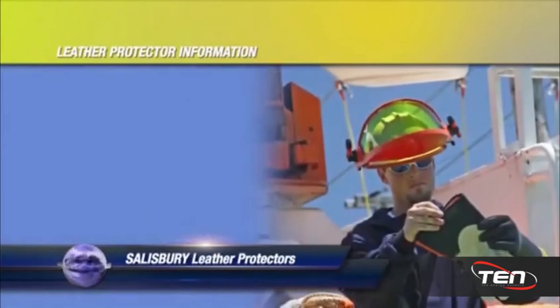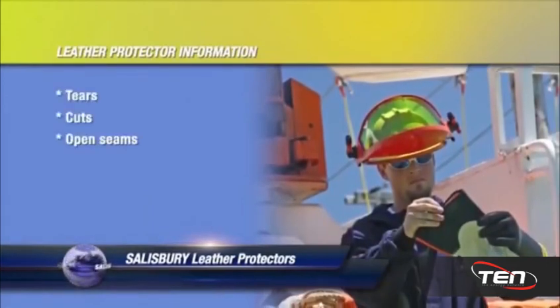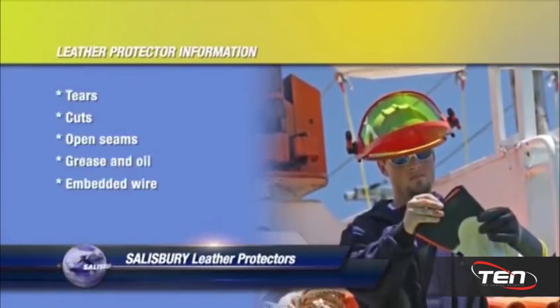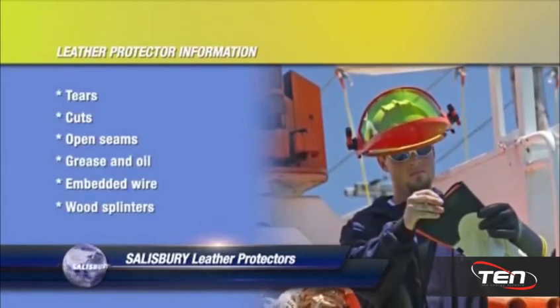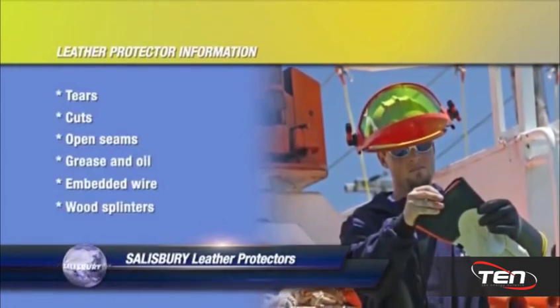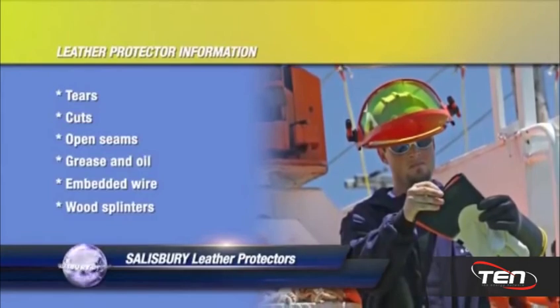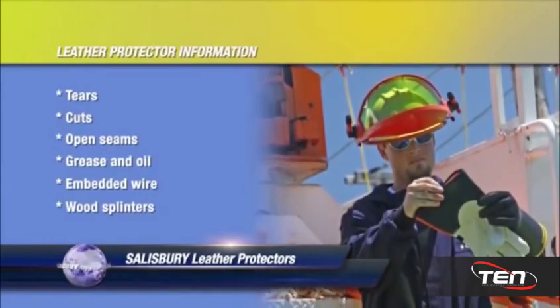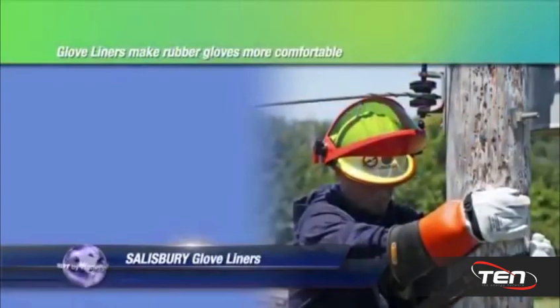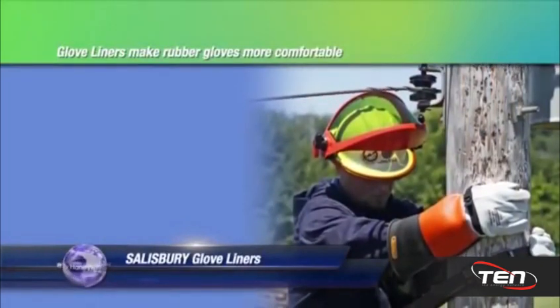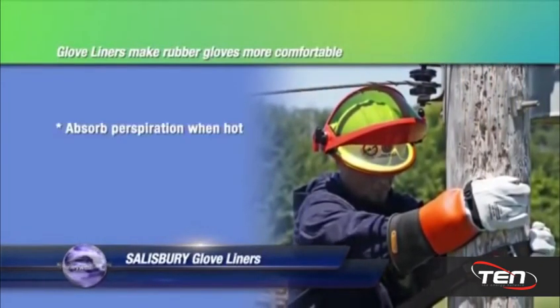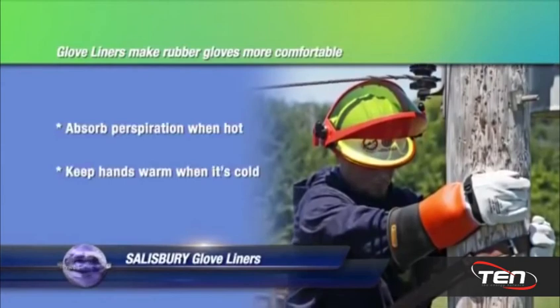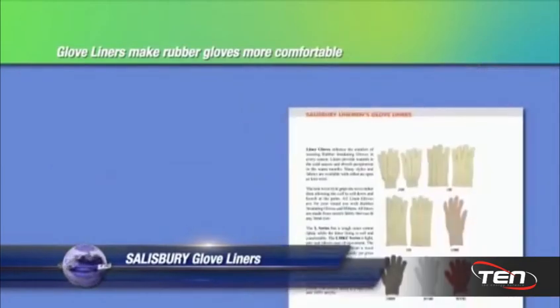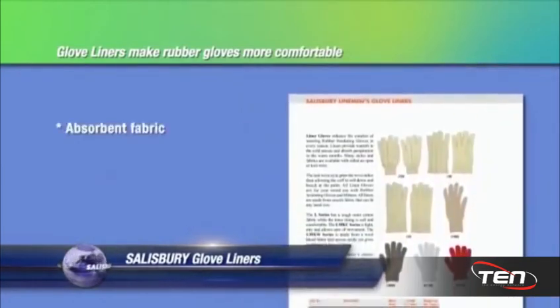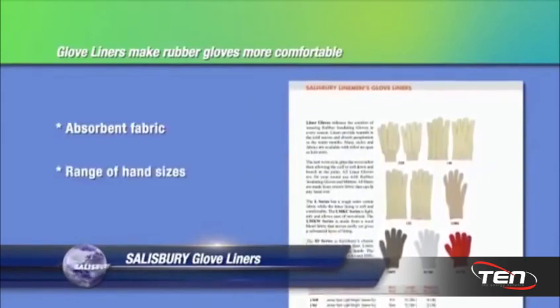Leather protectors should be inspected for tears, cuts, open seams, grease and oil, embedded wire, or wood splinters that could possibly come in contact with the rubber gloves. Protectors should be replaced when they are suspected of having any of these conditions. Glove liners can help to make rubber gloves more comfortable to wear. They absorb perspiration when it's hot and keep the hands warm when it's cold. Glove liners are made from absorbent fabric and accommodate a range of hand sizes.